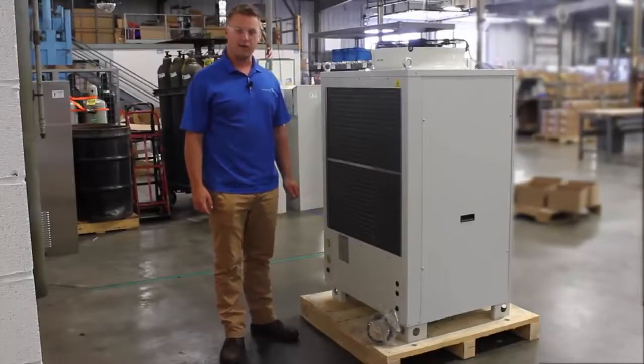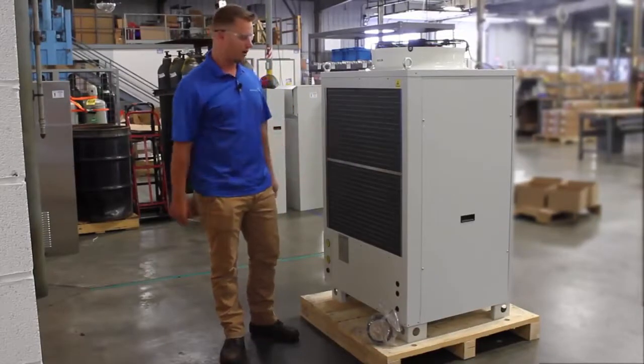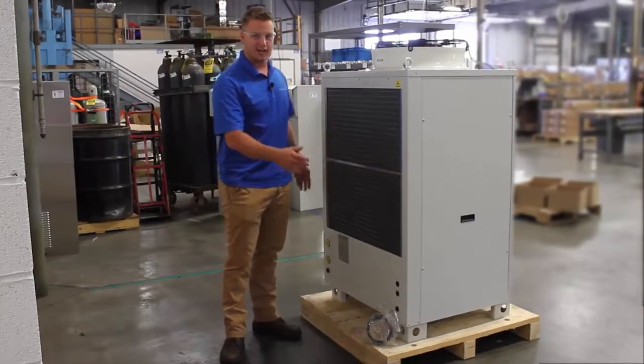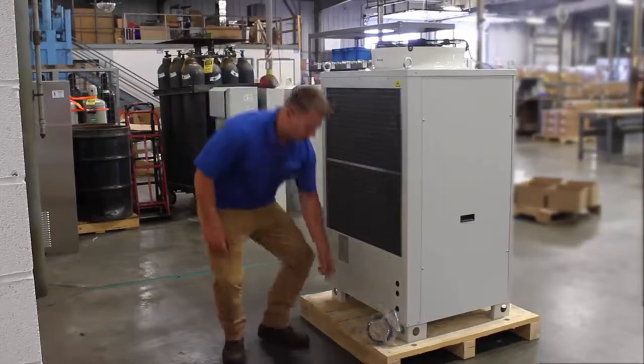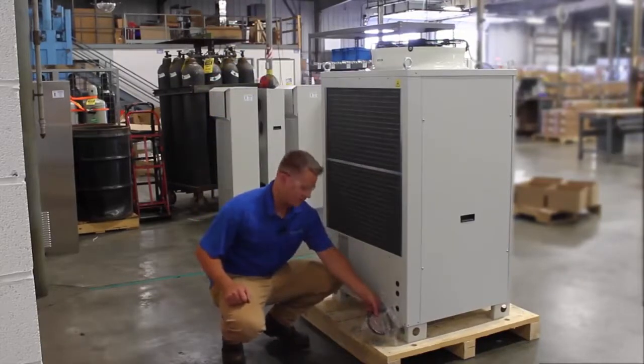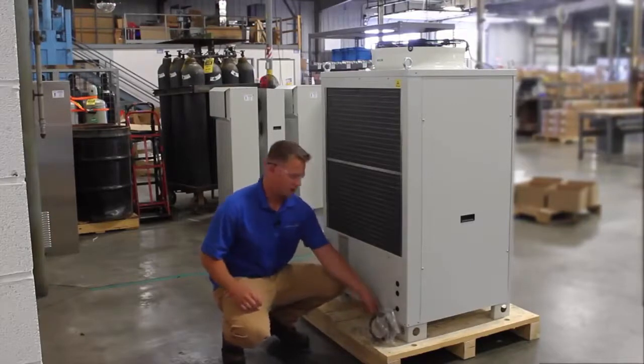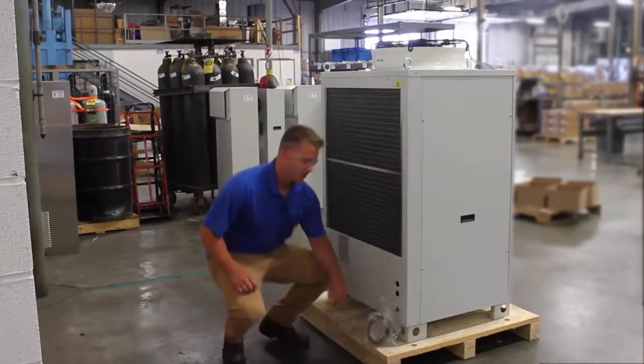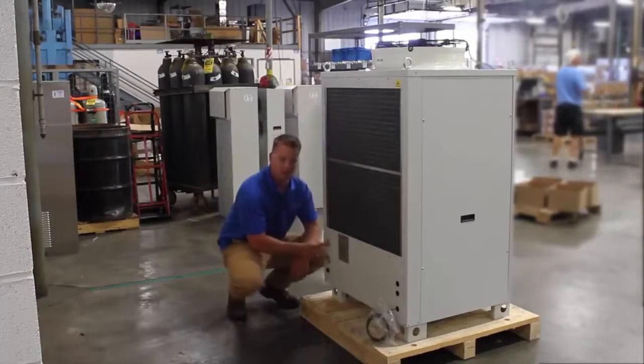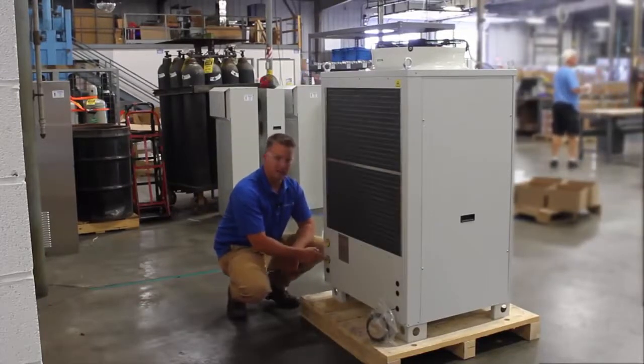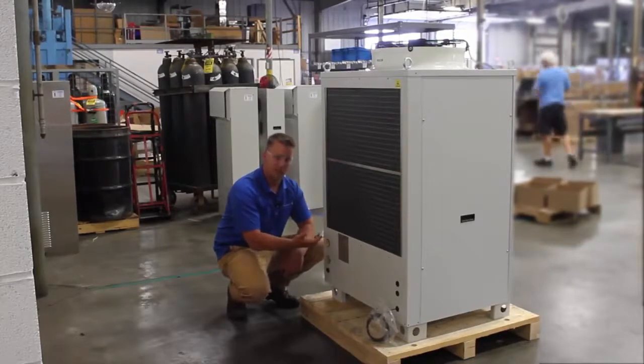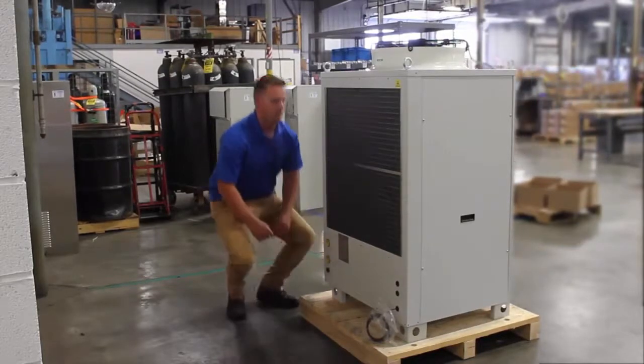All right, the next thing I want to take you to is the back side of the chiller. Right now we're on the condenser side of the chiller. On the bottom here, you'll see a temperature sensor. This temperature sensor is what I was referring to earlier. It'll read the ambient temperature so you can run in differential mode. Also, you'll see your hydraulic fittings over here where you connect your water lines when you set up the chiller in the initial install.